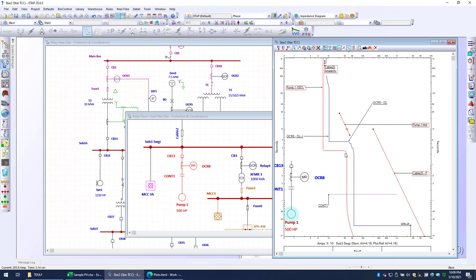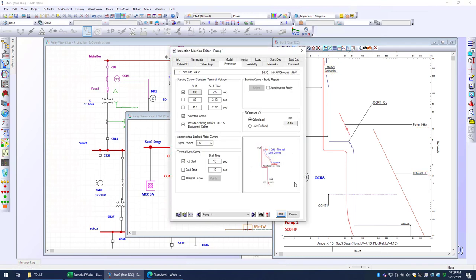We have the motor starting curve, but this is an approximation, and let me show you how. It's an approximation because essentially what we're saying is plot the locked rotor current, which is this section with an asymmetrical component, and at 2.5 seconds, transition to full load amps. And this is essentially the option that you see here. So I'm going to uncheck this option, and over on the right-hand side, select the acceleration study.